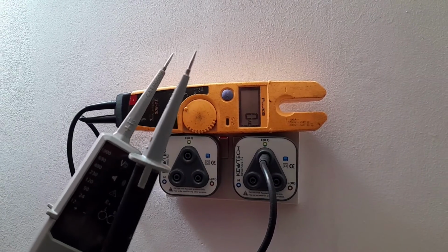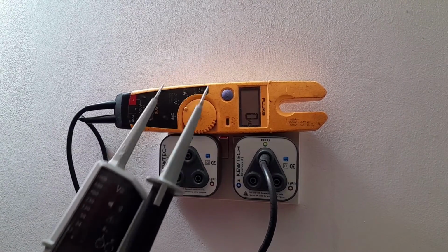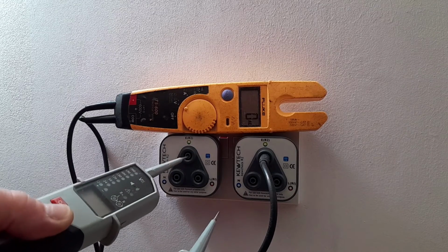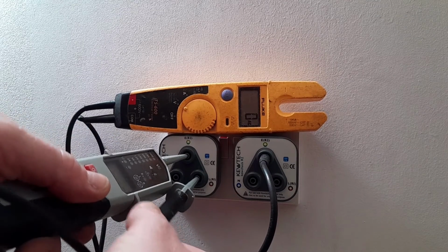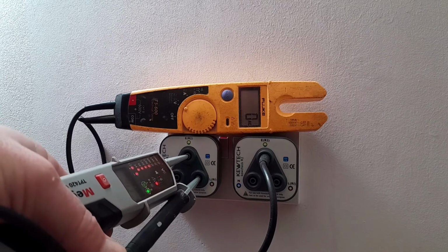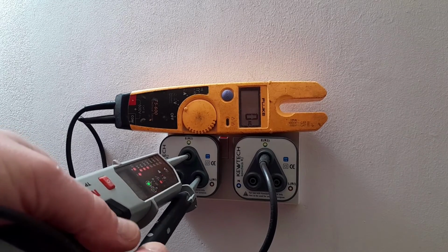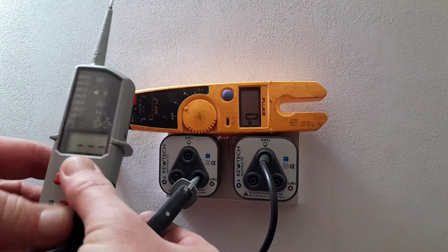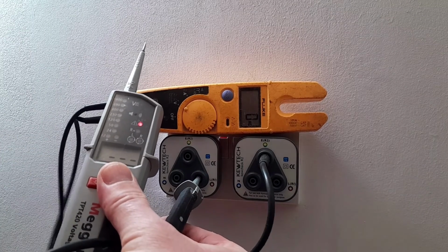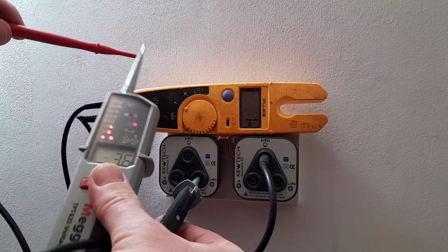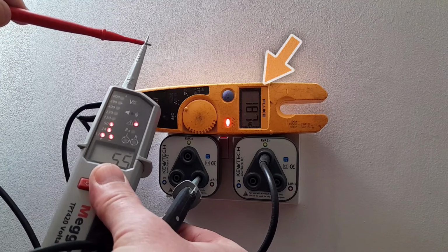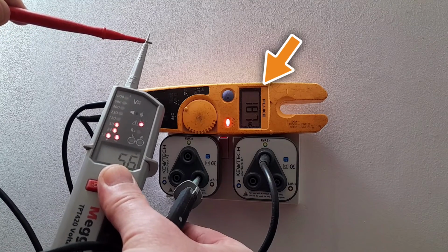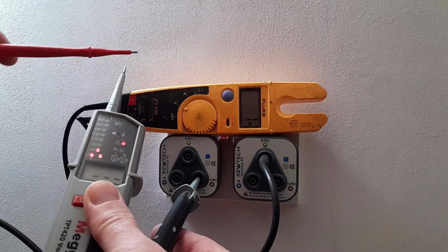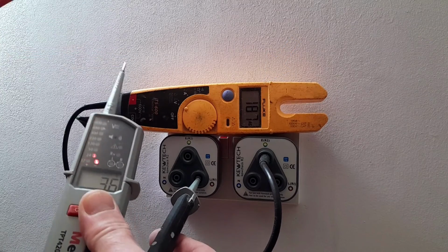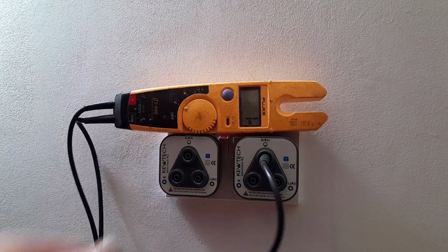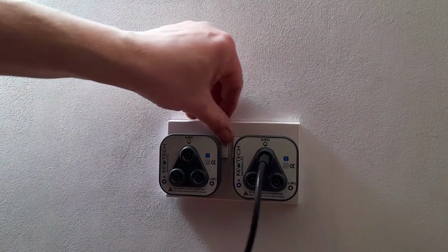And you might be tempted to take the covers off the probes and expose more metal so you can get into these socket adapters. But I wouldn't suggest you do that. I mean, you might get a reading. There you go, it's working, you're getting the connection. But again, you're never 100% sure how good that connection is. But the thing to remember is, if it is live, you'll notice there on the Fluke tester, I'm testing the other end of that probe, and we've got a voltage on that. If you've got a live connection on one end of your voltage tester, the other end of that probe is going to become live as well, and you can get a shock. So it's best to use the proper connections, do it right.